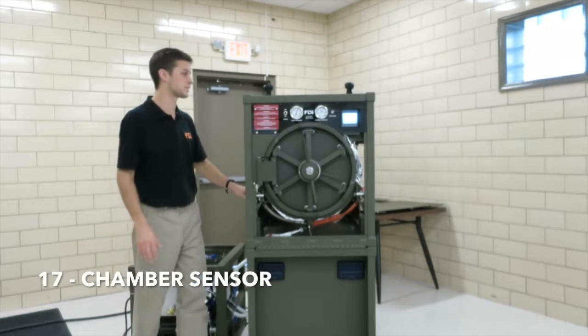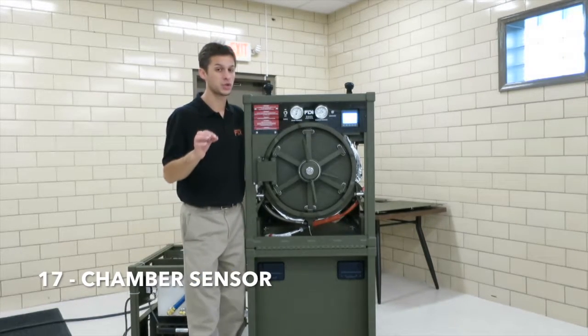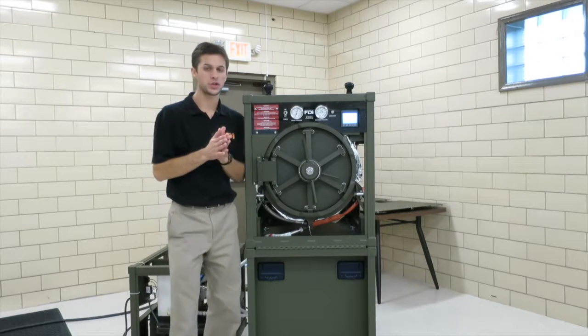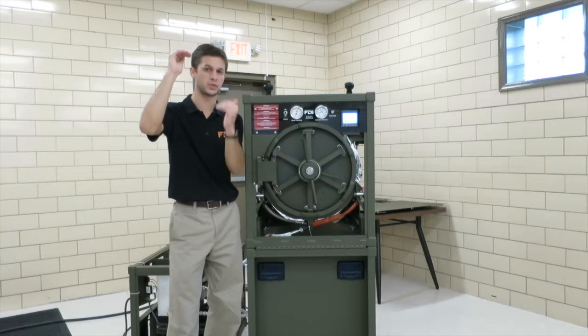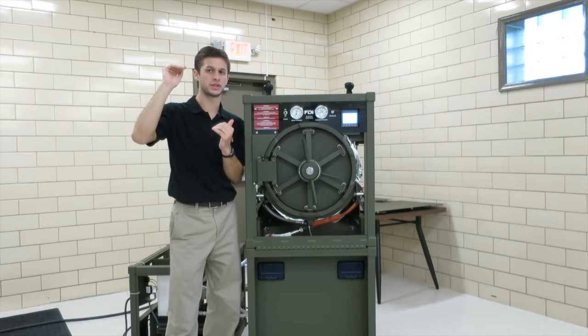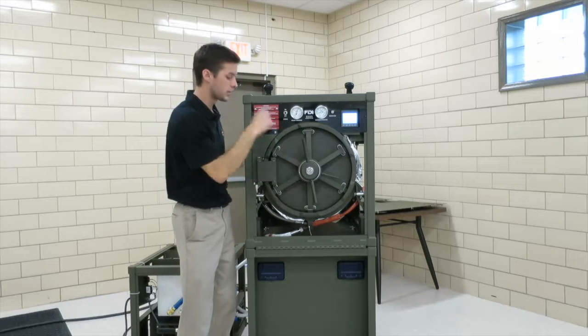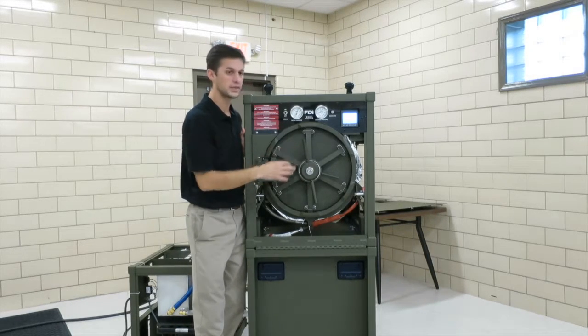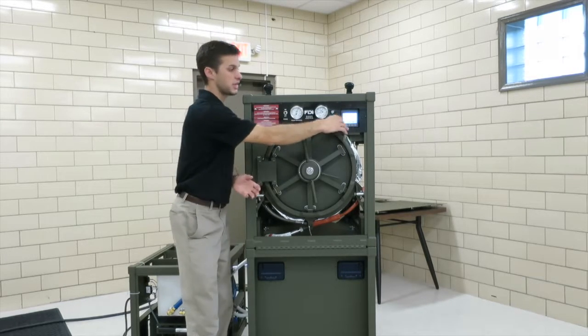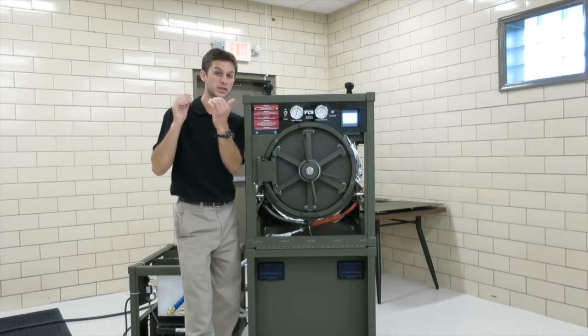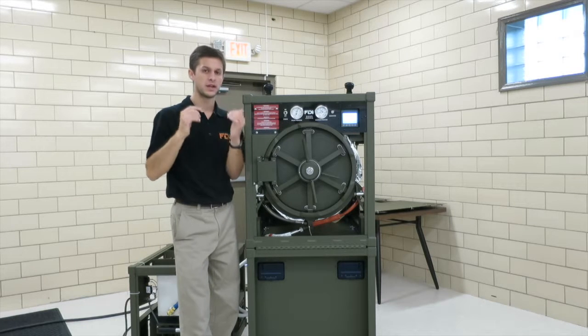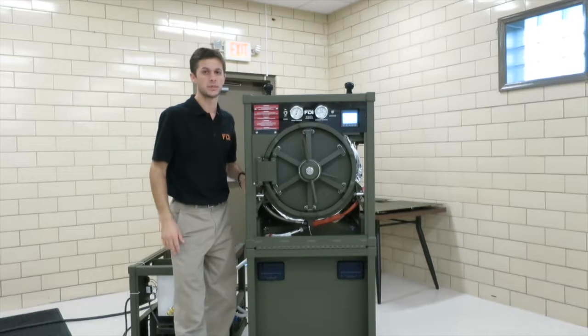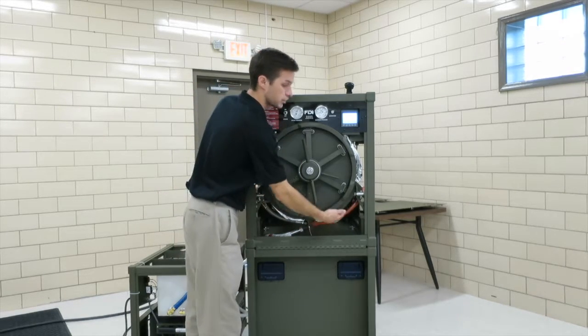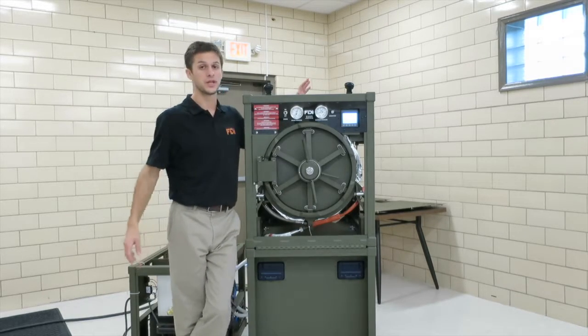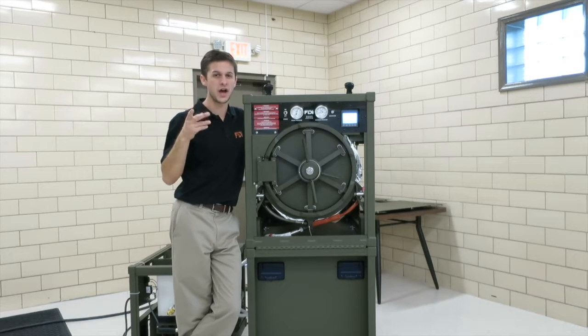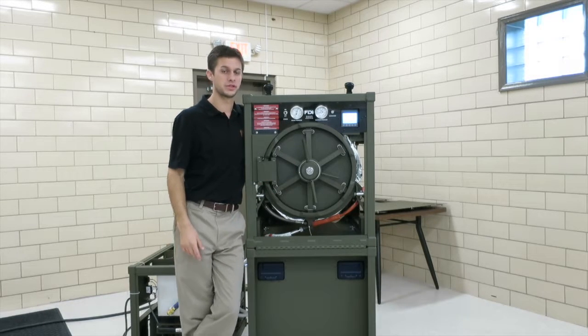Number 17 is chamber sensor. The reason it's chamber sensor is that it's not temperature or pressure specific. Since temperature and pressure are directly proportional, as temperature rises, pressure rises, if there's a big enough difference between the two, you'll get a 17 chamber sensor alarm. So if the steam temperature in the chamber is, say, 273 degrees, the PLC knows approximately what pressure the chamber should be at. If it was, say, way low, the PLC would know something's off and that pressure and temperature are not proportional, and it would throw a 17 chamber sensor alarm. So you would know there are possibly some problems with your temperature measurement equipment, possibly your chamber pressure sensor. If the sensors are not working together, you'll know one of them is malfunctioning.